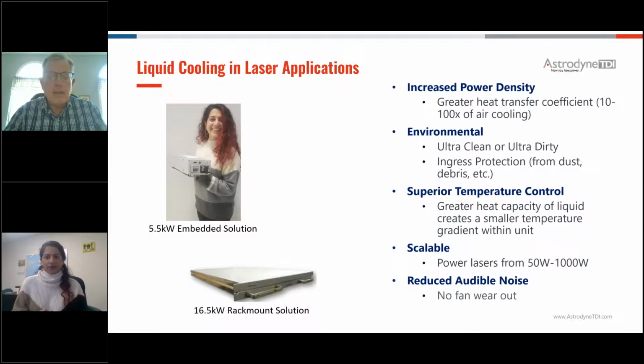The last thing is that a liquid-cooled solution has no fans. If you're ever in proximity of a high power fan-cooled solution, they're loud, especially when producing full power - sometimes it's hard to hear what's going on next to them. The nice thing about liquid-cooled units is that if the pump is located remotely, the power supply is basically silent, which can be a big benefit in applications like a semiconductor test environment where people are talking a lot. Liquid cooling can really come into play with regard to the ergonomics of the unit.